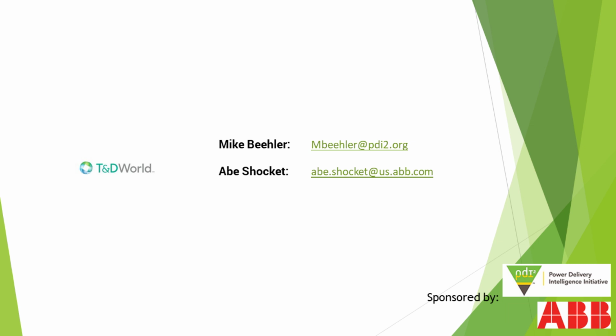I can say, utility standards never say just "meet IEEE C37.74" and what year, and that's all it says. It's always a multi-page document that has a lot of special considerations that are required for that utility. Everybody's got different environments, different practices. So we always review these things in great detail here and provide design drawings for approval before we bother to build any gear. So I think it's not surprising that the standard for the utility is quite an adaptation beyond what's in the industry spec.